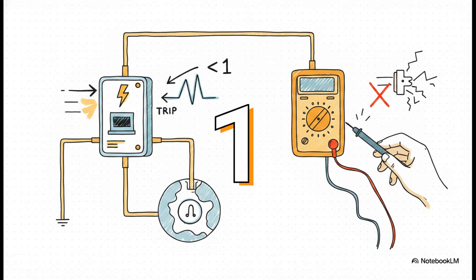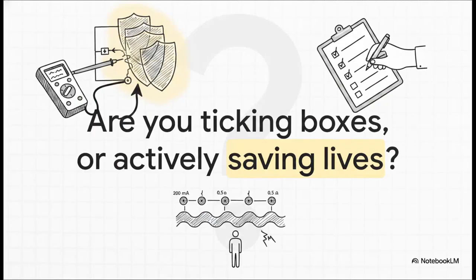literally be catastrophic. So, as we wrap up this explainer, I want to leave you with a question to think about. When you're out there in the field with your low-resistance ohm meter in hand, are you just ticking boxes on some government form, or are you actively proving that the invisible shields in that electrical system are intact and ready to save a life? Because remember, these strict, legally mandated tests are the absolute only thing standing between a hidden electrical fault and a tragic accident. Every visual check, every 200 milliamp test, every 0.5 ohm reading, it all matters. Stay safe, trust your calibrated equipment, and stay incredibly focused out there.